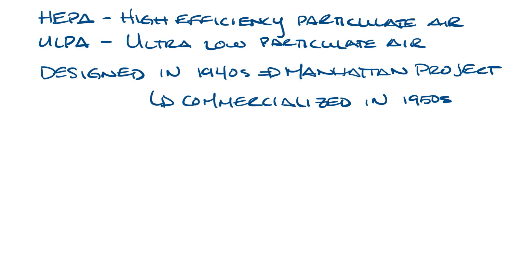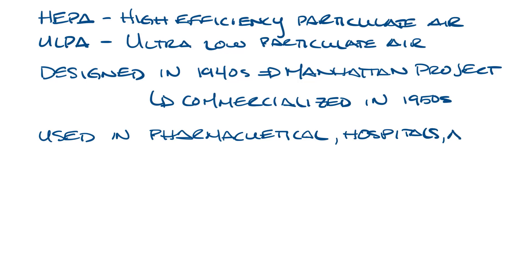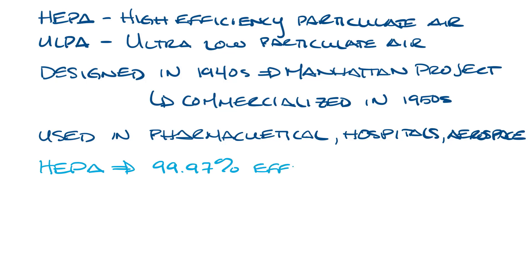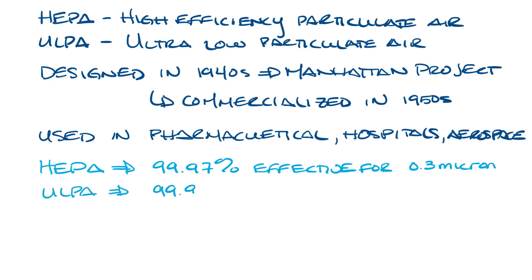Now you see HEPA filters in many critical environment applications like the pharmaceutical industry, hospitals, and aerospace, just to name a few. HEPA filters are 99.97% effective at eliminating particulate matter of 0.3 micron diameter or larger, and ULPA filters are 99.999% effective at removing particulate matter of 0.12 micron diameter or larger.